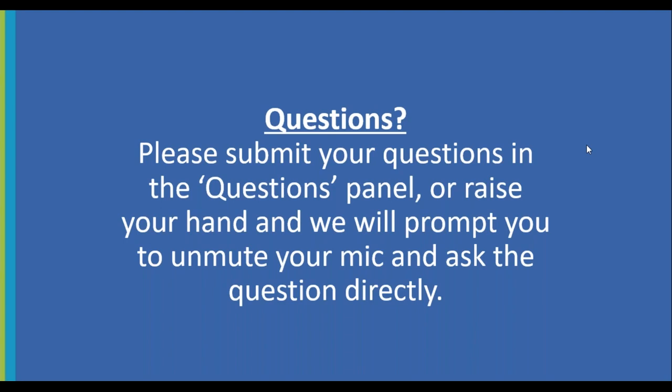Well, thank you. A question here from Celine Pellerin. Firstly, she thanks you for an interesting presentation. And she asks, when doing a sorption and desorption cycle experiment, what is good practice regarding the relative humidity level when doing the 0 and for sample insertion? Should it be at 95% to avoid static buildup, or close to 0 to keep the sample dry?